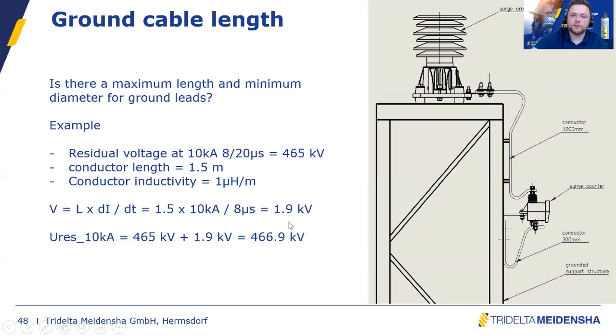So two things we have to consider. One thing is the safety aspect. That's why you should never touch the upper conductor of the surge arrestor. Under lightning or discharge conditions, there will be a dangerous voltage drop on the conductor, even though it's grounded. And the residual voltage of the surge arrestor is changing.